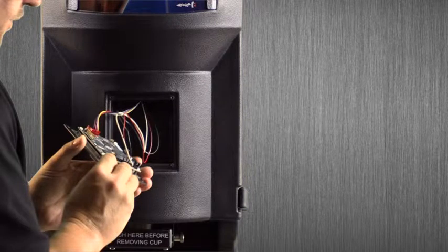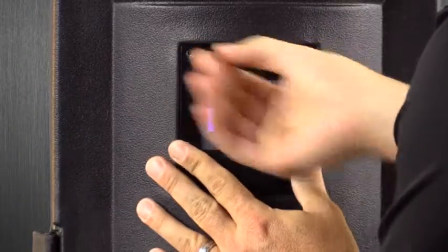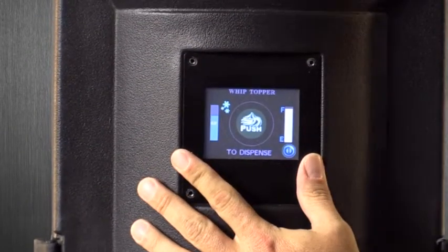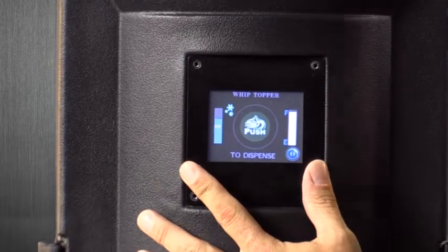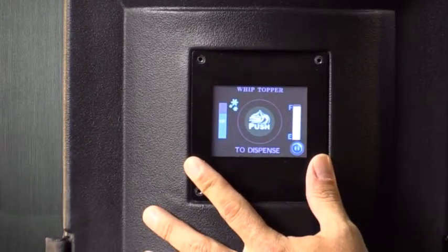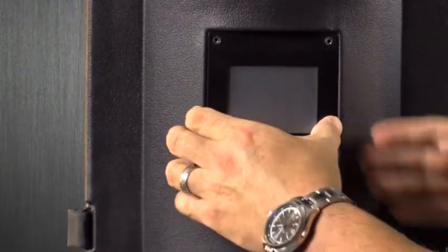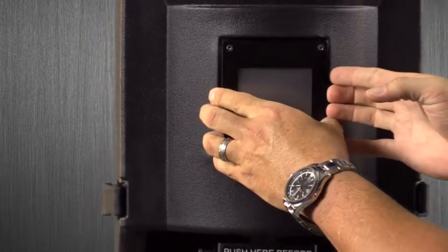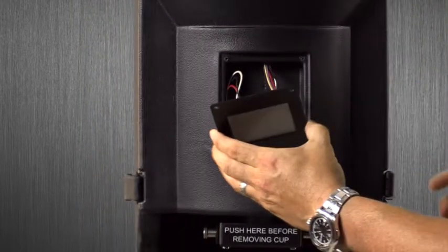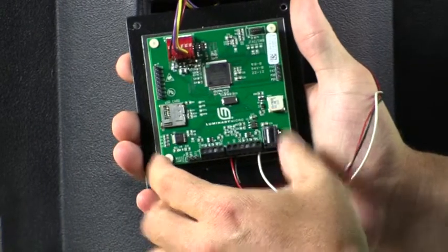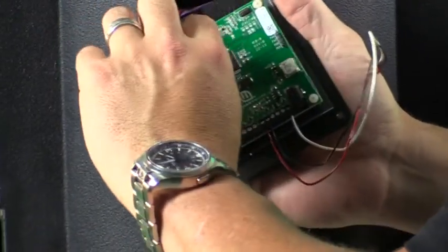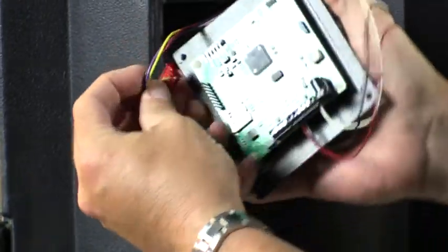If the unit is still not responding properly, we will need to power down the unit and then remove the main touchscreen display that is secured to the front door with the 4 Phillips head screws. Once the last screw is being removed, make sure that the display is supported to keep the display from falling and possibly damage any main circuit board wiring harnesses that are attached. Unplug the red multi-wire connector located on the back of the circuit board and plug it back in. You may power up the unit and verify that the display is operating properly.